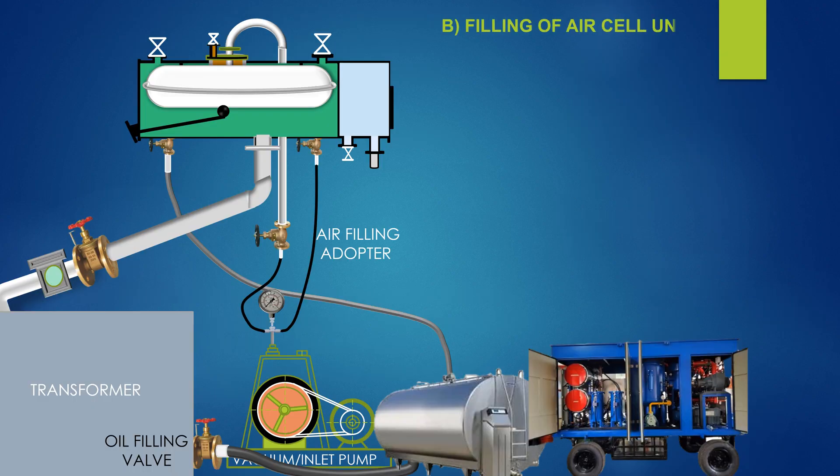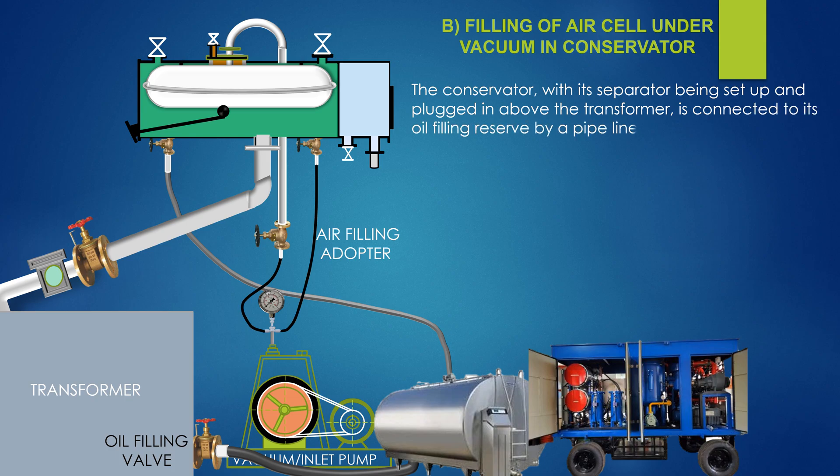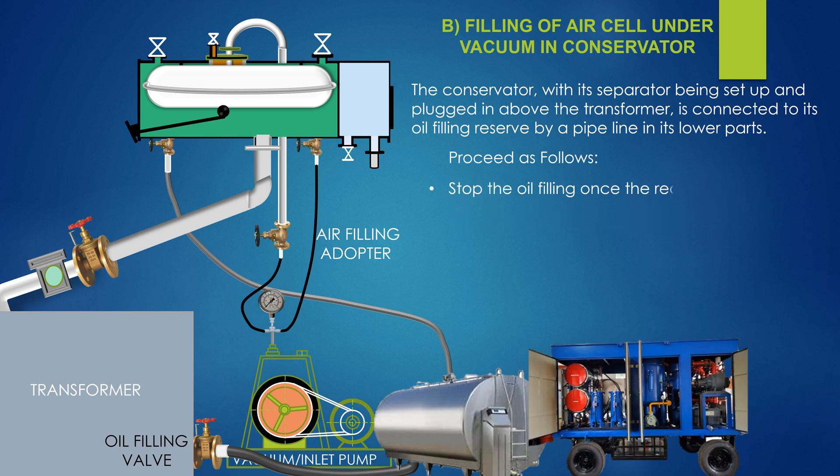Filling of air cell under vacuum in conservator. The conservator with its separator, being set up and plugged in above the transformer, is connected to its oil filling reserve by a pipeline in its lower part. Proceed as follows: create a vacuum in the separator. With the same source of vacuum, create a vacuum in the conservator. Open the oil filling valve of the transformer; because of the vacuum in the conservator, the oil level rises automatically. Stop the oil filling once the required volume in the conservator is attained.